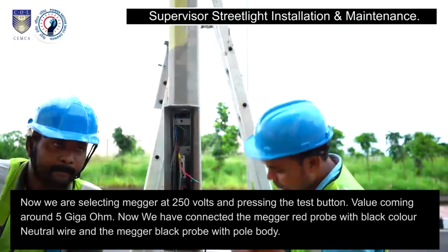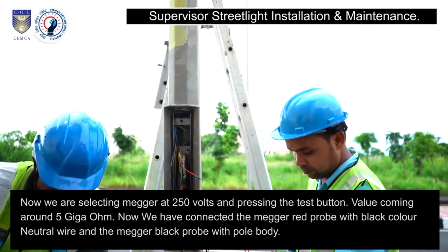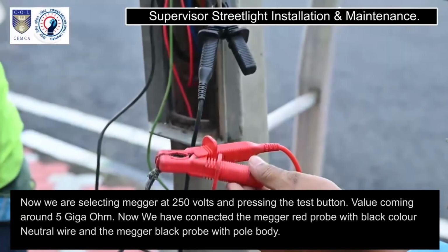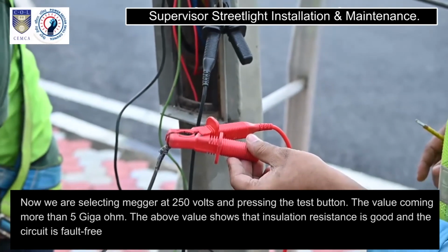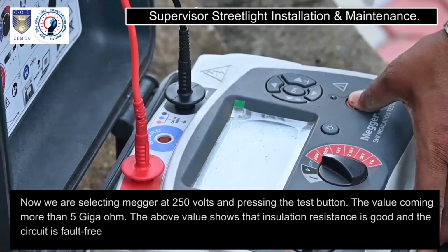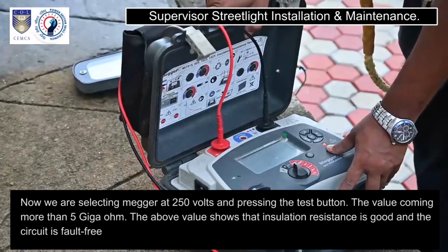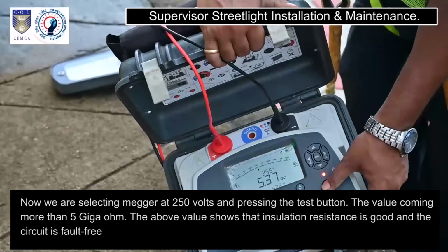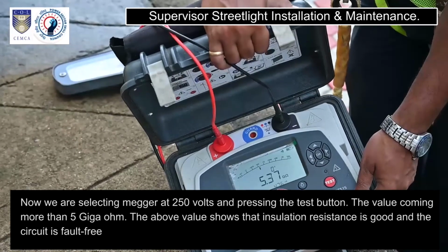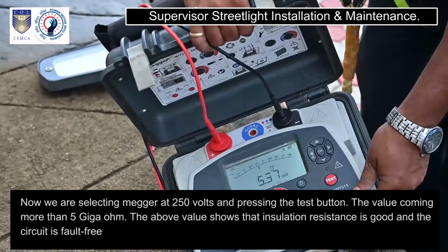Now we have connected the megger red probe with black color neutral wire and the megger black probe with pole body. Now we are selecting megger at 250 volts and pressing the test button. The value coming more than 5 gigaohm. The above value shows that insulation resistance is good and the circuit is fault-free.